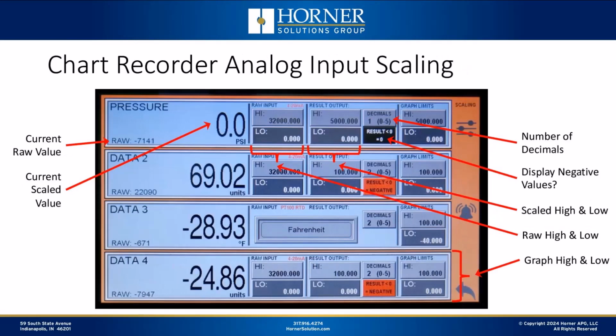Now, in addition to that sort of configuration, you also have the ability, and it's important, of course, to be able to scale each particular channel to engineering units. So let's say, for instance, we've got a pressure sensor, and that pressure sensor has a 4 to 20 milliamp output. And let's say that at 4 milliamps, it represents 10 pounds per square inch, and at 20 milliamps, it represents 100 pounds per square inch. So on the raw input side, in this case, you would configure the minimum and the maximum value of the A to D conversion for that input channel. And generally, with this product, 0 is going to be the minimum and 32,000 is going to be the maximum. So those are kind of the raw digital converted values coming in from the sensor.